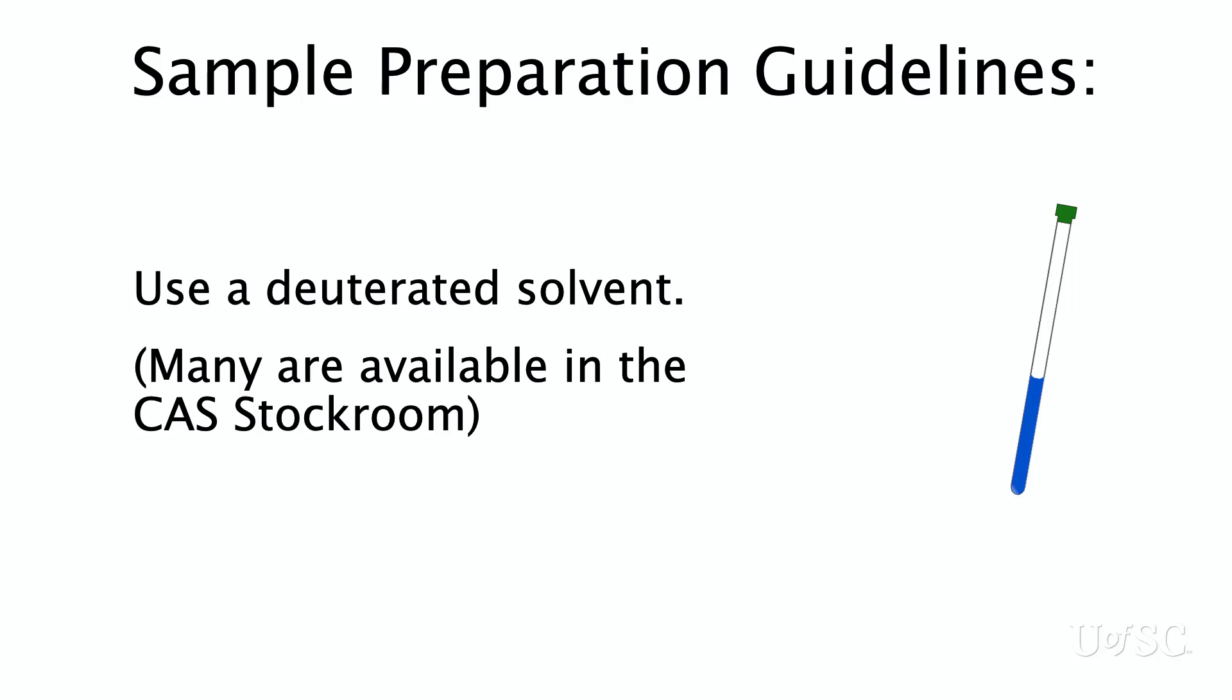Use deuterated solvents. The instrument uses the deuterium for locking and shimming in routine operation. Replacing the protons in the solvent with deuterium also removes them from interfering with observing your dilute samples. We have some tricks for running samples with no deuterium, but this is not a routine experiment.